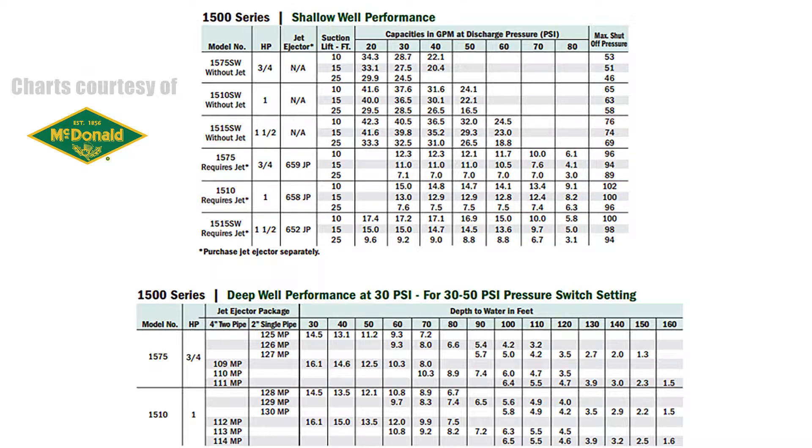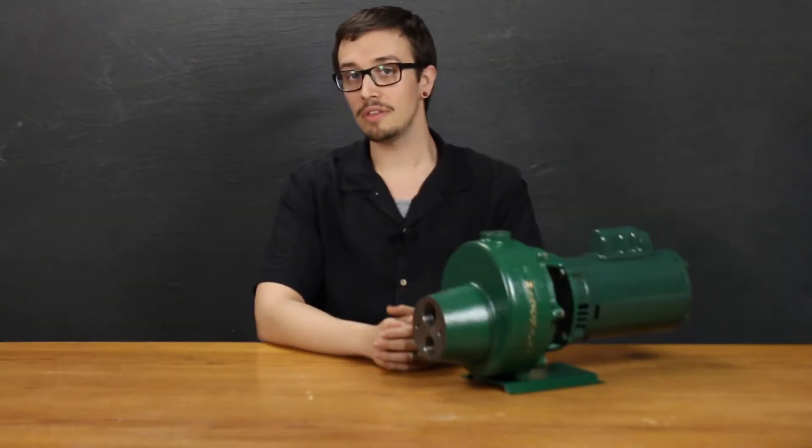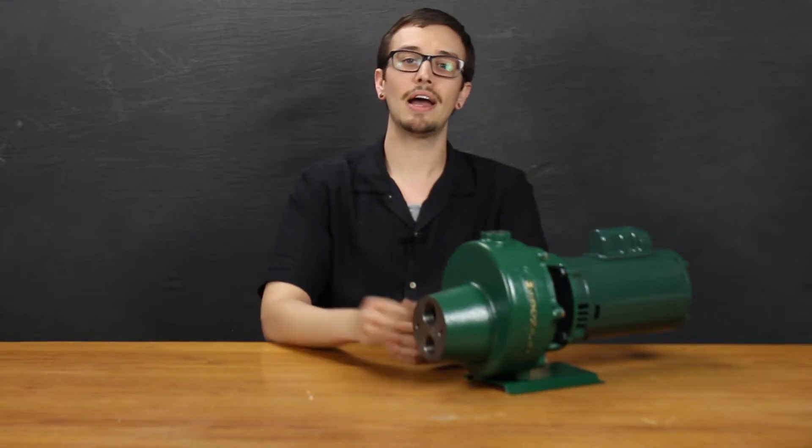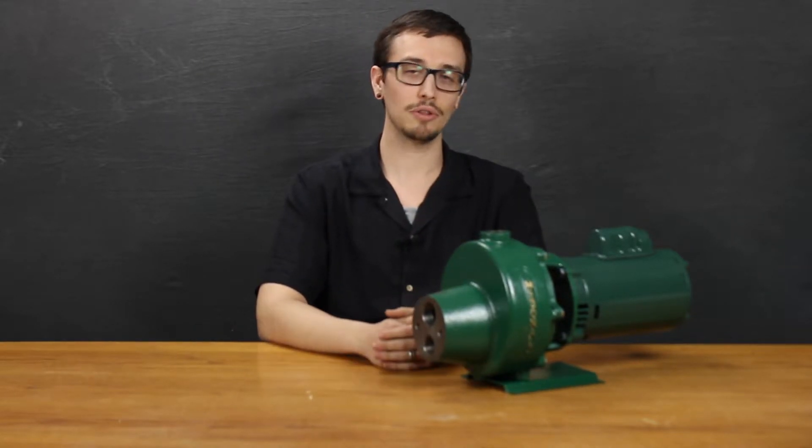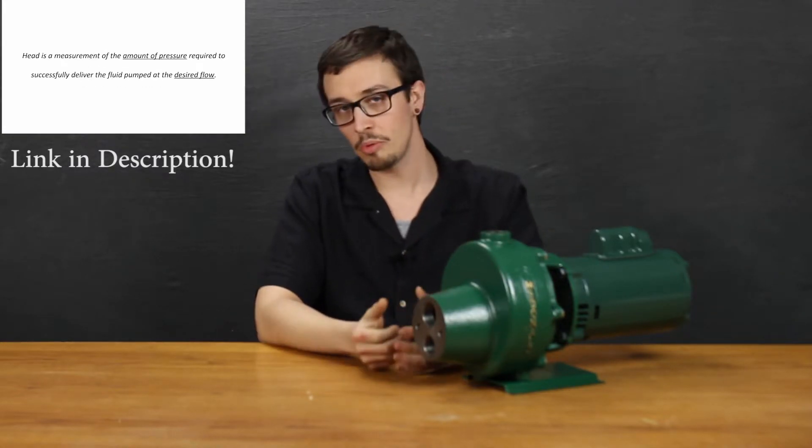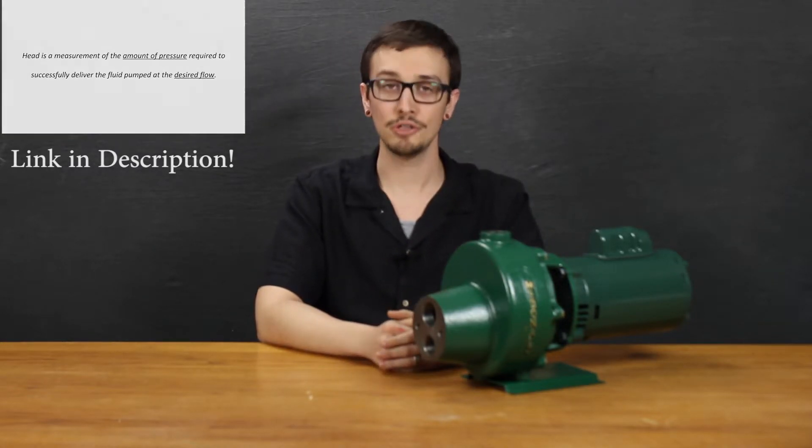The maximum flow with the jet is 17 gallons per minute and 42 gallons per minute without. Typically, the shallow well jet is used in applications where you need to achieve a higher head pressure and don't mind sacrificing a little bit of flow. If you're a little hazy on the details of pump head, we've prepared a video. You can find that in the description below.